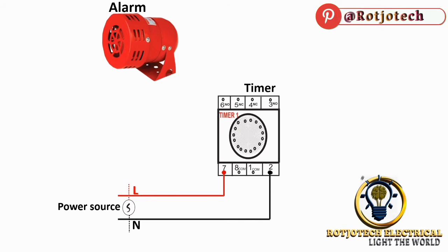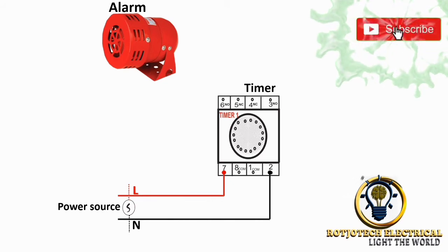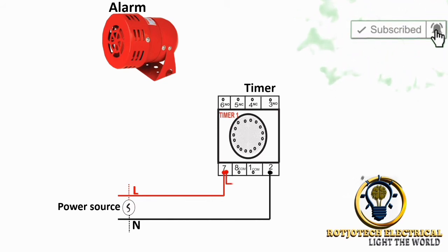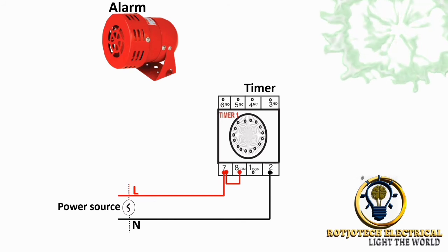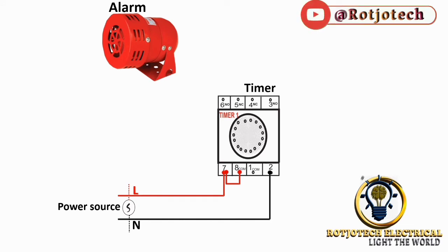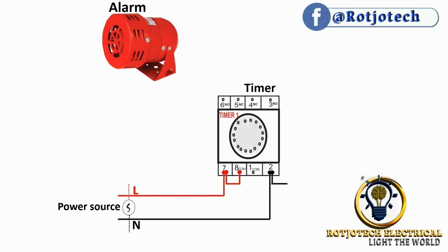But to supply power to the common of this timer, we are going to loop from terminal number 7 to terminal number 8. Now that we have looped from terminal number 8, we are going to connect neutral to the alarm, and we are going to connect it from terminal number 2 straight to the alarm.